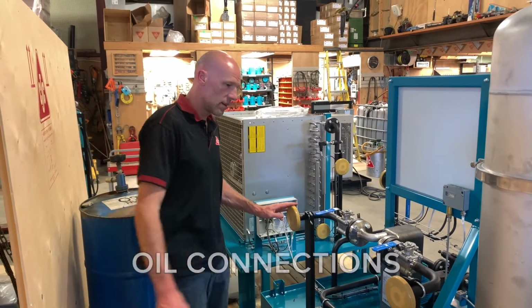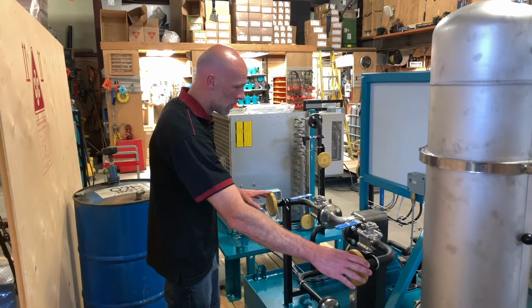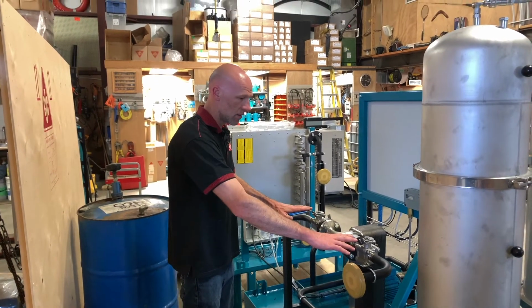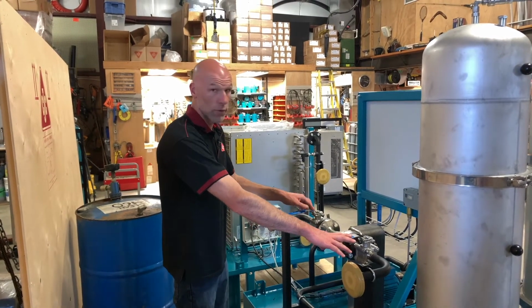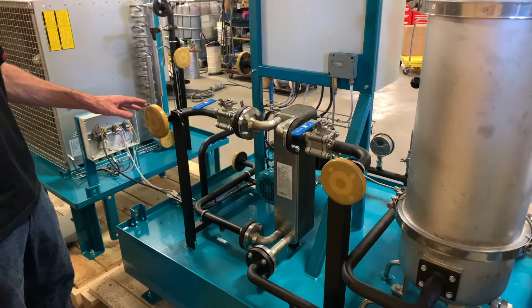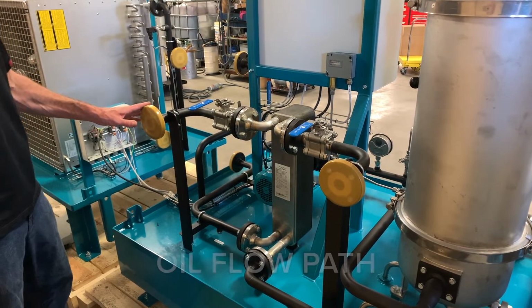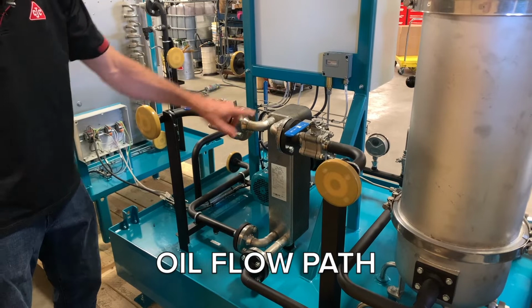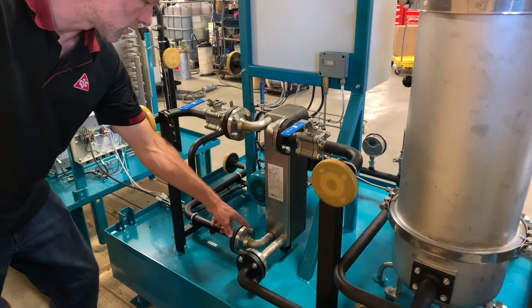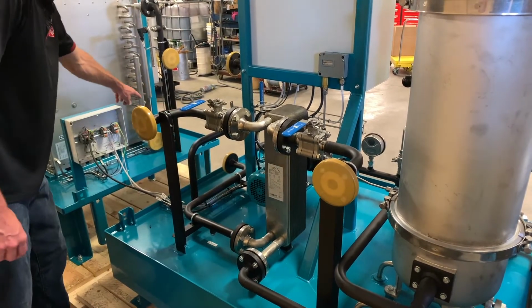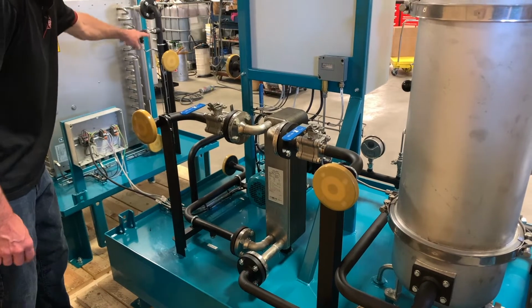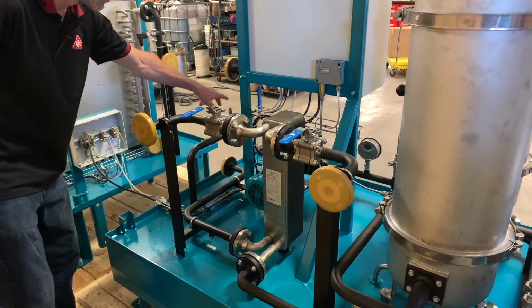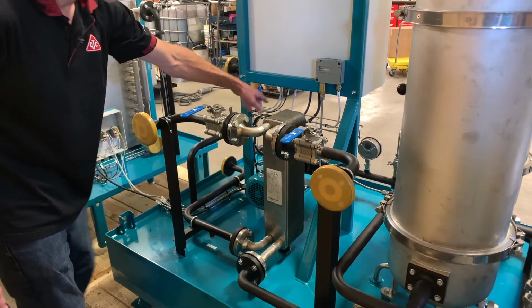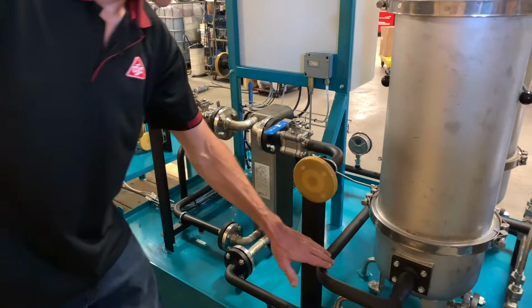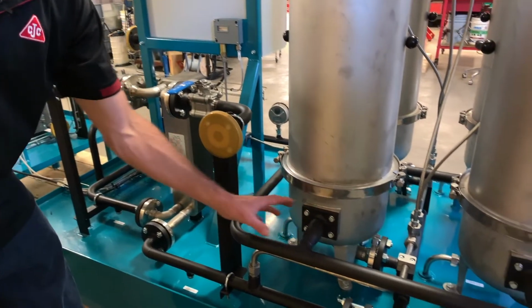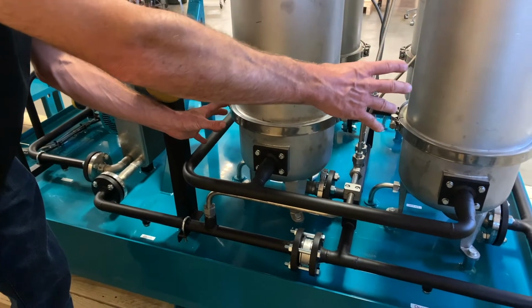We've got the inlet here and the outlet here, and both have built-in shut-off valves that are also lockable. So the oil flow in the unit comes in through the inlet, runs through the hot side of the heat exchanger, out to the fan cooler. The colder oil comes back into the skid and goes into the main pump. The pump feeds this inlet manifold, supplying oil to each of the filter housings in parallel.